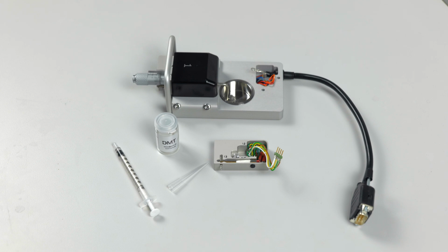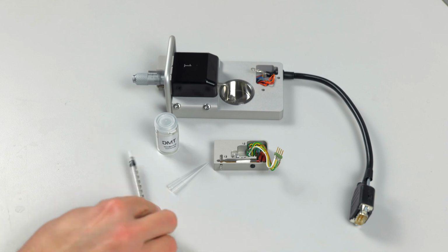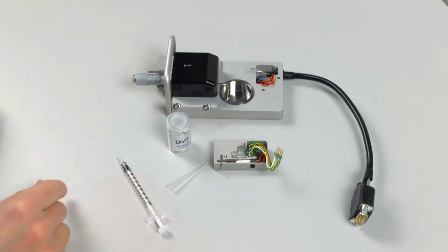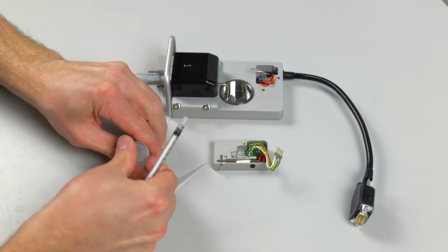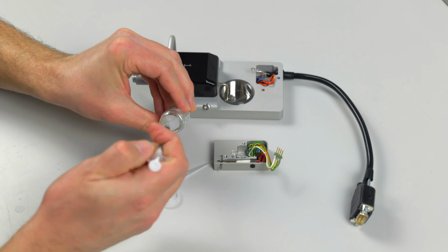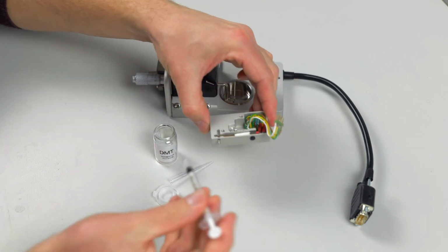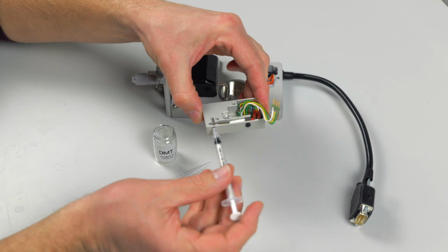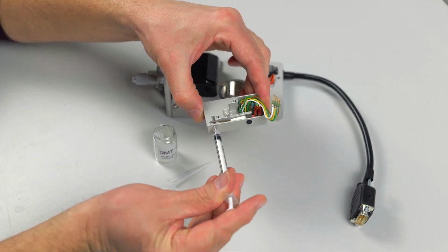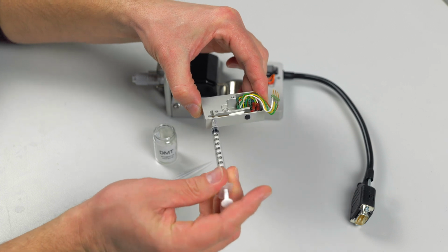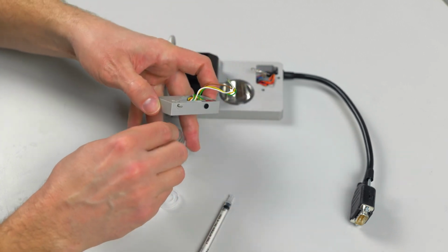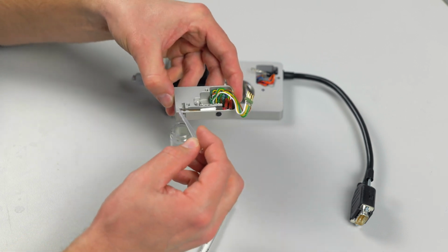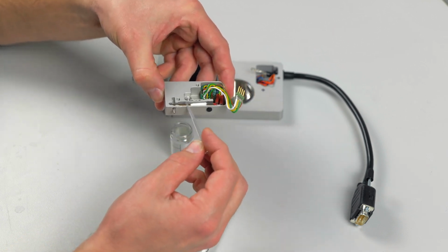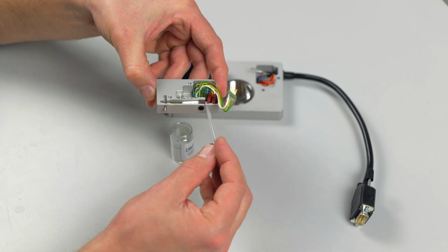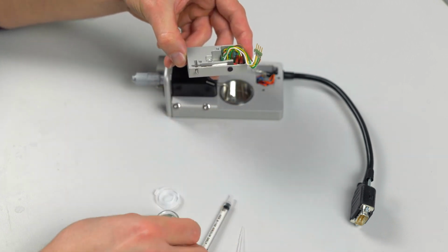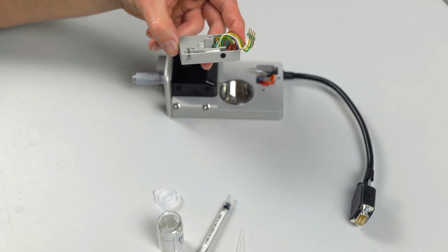To do this, we will first have to grease it. So you'll need a 1ml syringe, a pipette tip, and then the clear silicone grease. Put some clear silicone grease into the 1ml syringe and then use that to go over the transducer pin. You can then take your pipette tip and run some grease along the front edge of the transducer housing. This will prevent buffers, other liquids from getting inside the transducer housing and damaging the transducer.